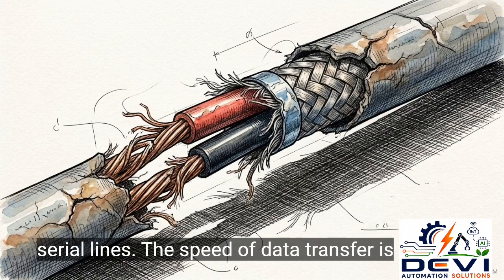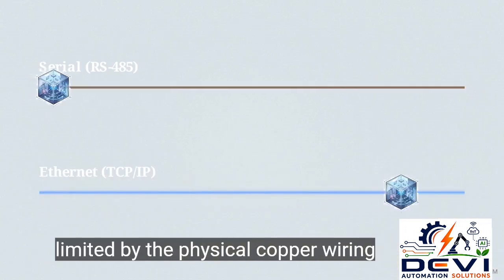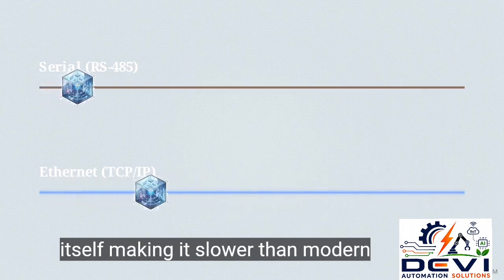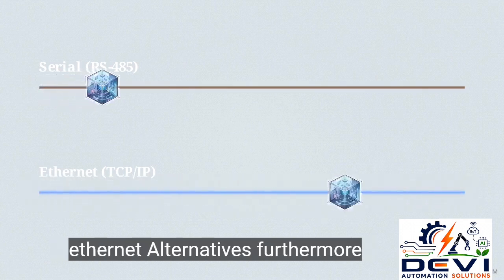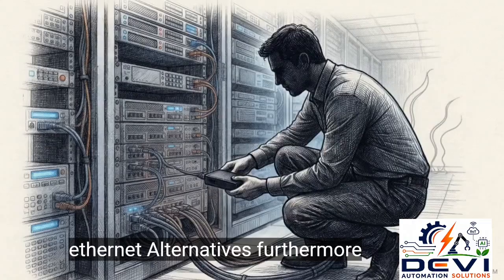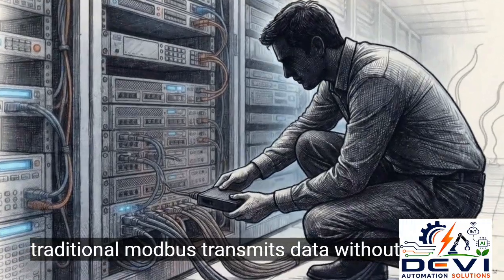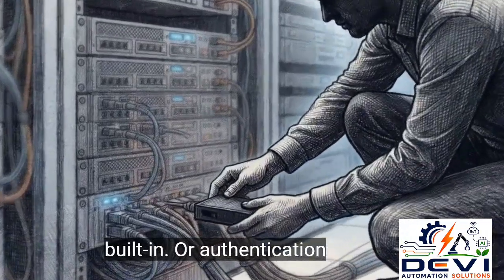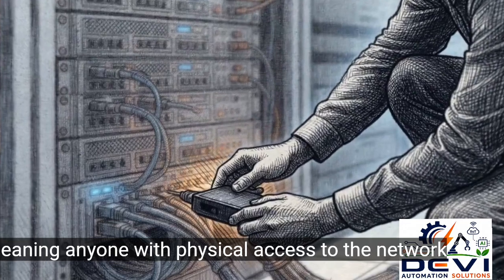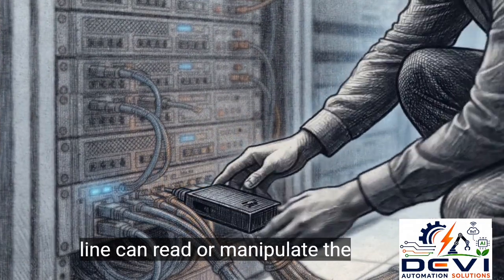Over older serial lines, the speed of data transfer is limited by the physical copper wiring itself, making it slower than modern Ethernet alternatives. Furthermore, traditional Modbus transmits data without built-in encryption or authentication, meaning anyone with physical access to the network line can read or manipulate the data.